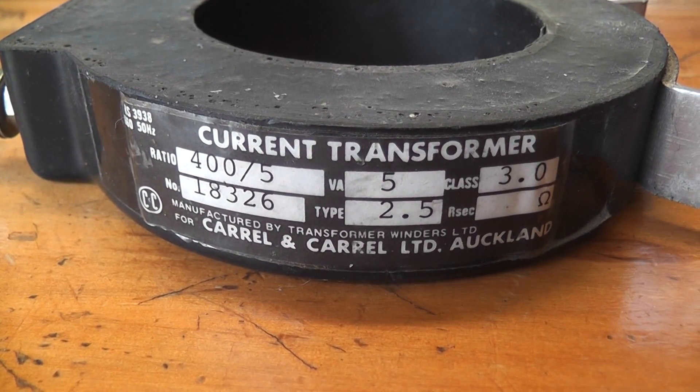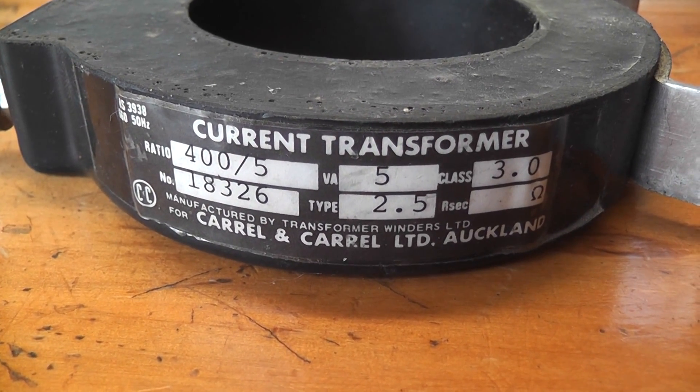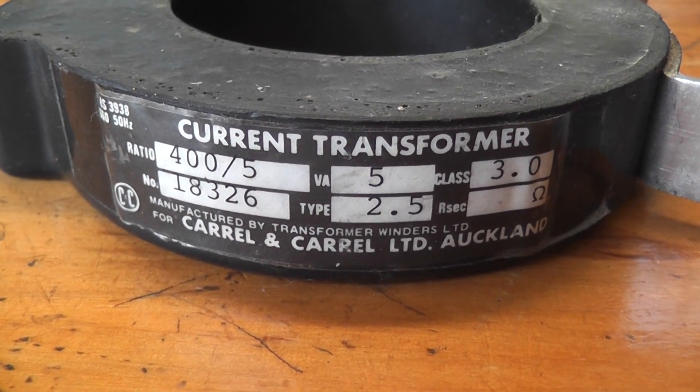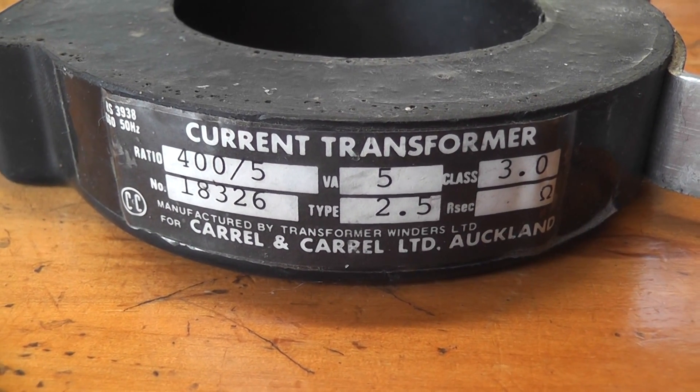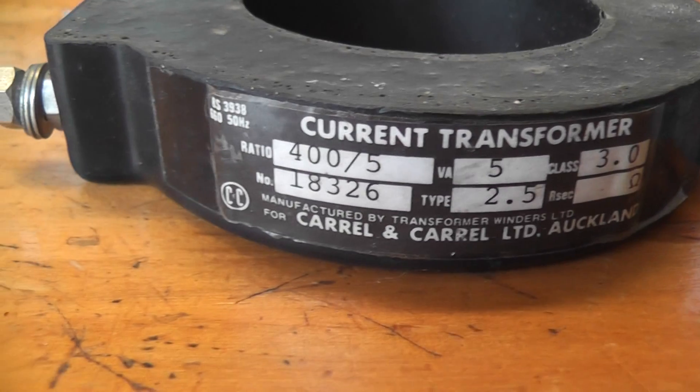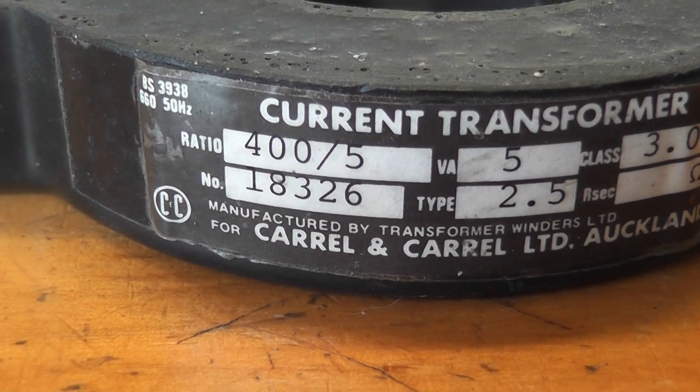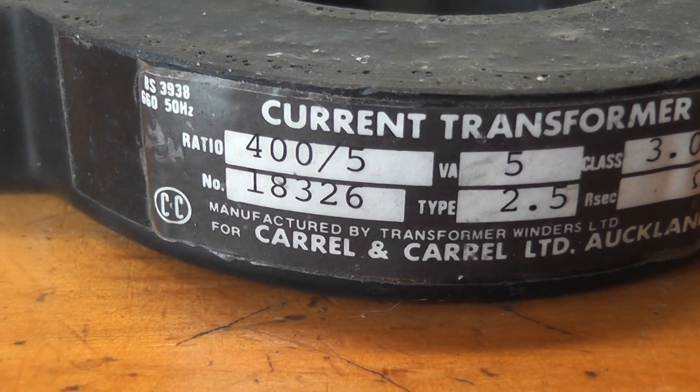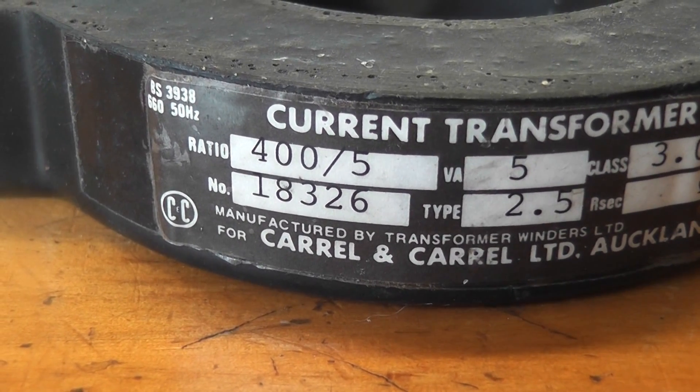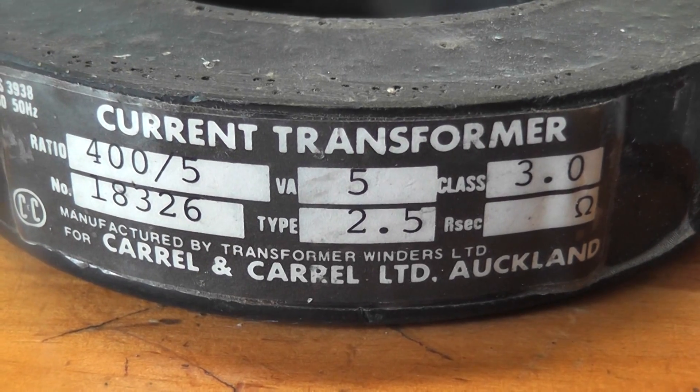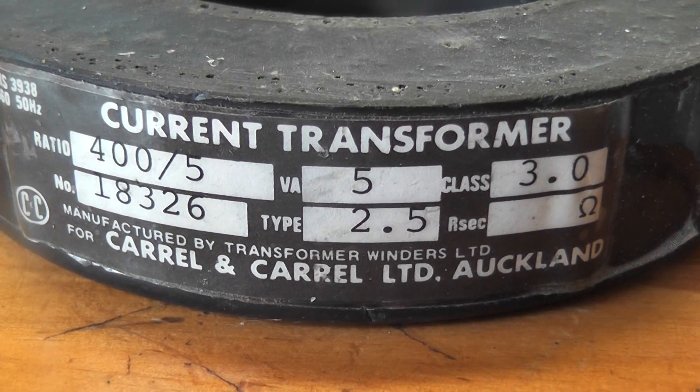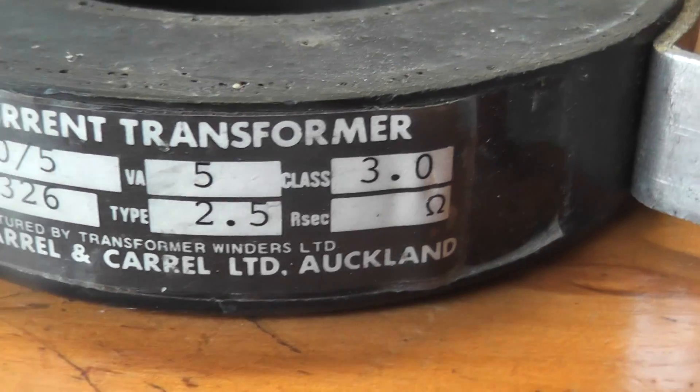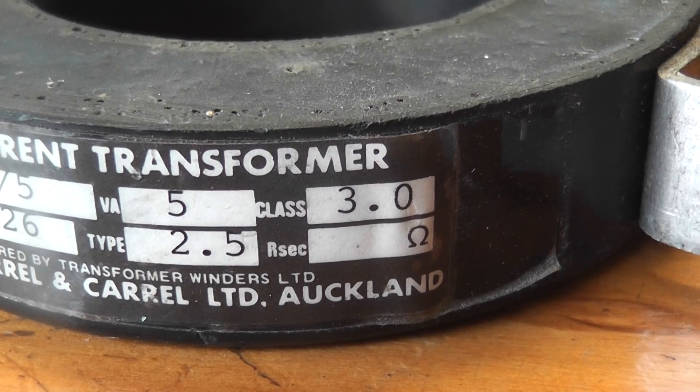In this video I'm just going to have a little talk about CTs or current transformers. This particular CT you see here is a 400 ampere primary rated to 5 ampere, 400 to 5. That means 400 ampere goes through the actual CT and it gives 5 ampere to the meter. The CT is rated at 5 VA, volt ampere, class 3 so it is not a very accurate CT, 3% error.